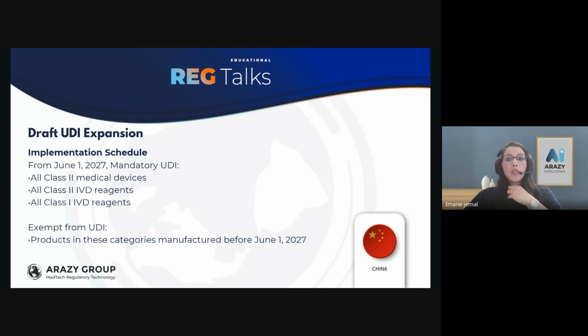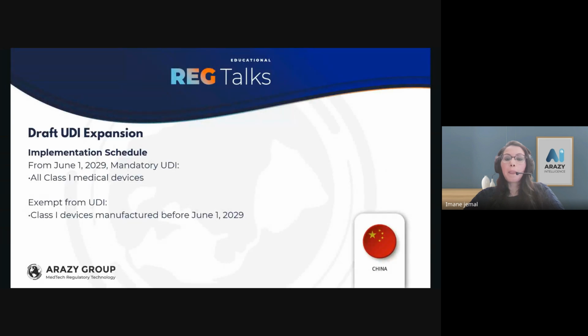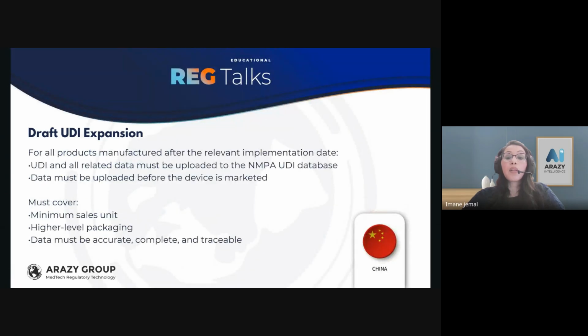From June 1st, 2027, UDI will become mandatory for all Class 2 devices and all IVD reagents at Class 1 and Class 2 level. Anything produced before that date is exempt. So starting from June 1st, 2027. Class 1 devices have a later deadline. UDI becomes mandatory only for products manufactured after June 1st, 2029. So it is about the date when the device is manufactured. And every device made after the cut-off date must have its UDI and packaging data uploaded to the NMPA database before entering the market.